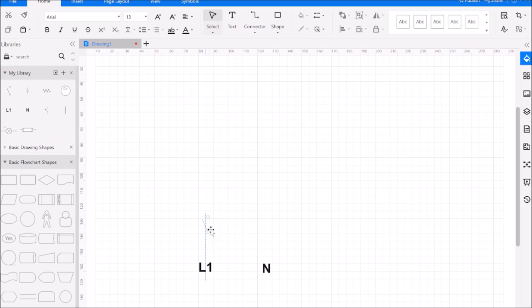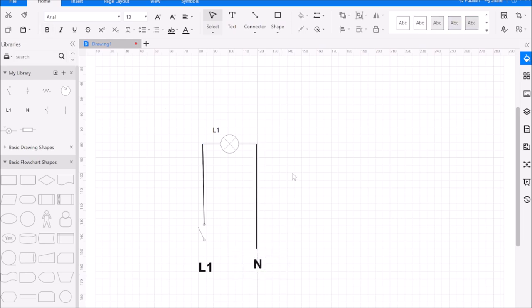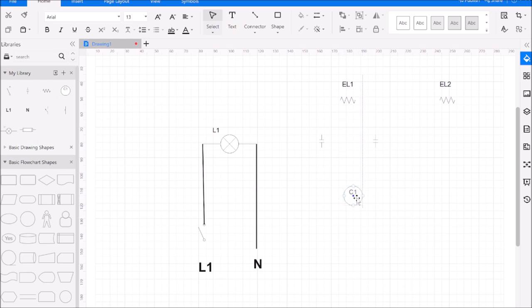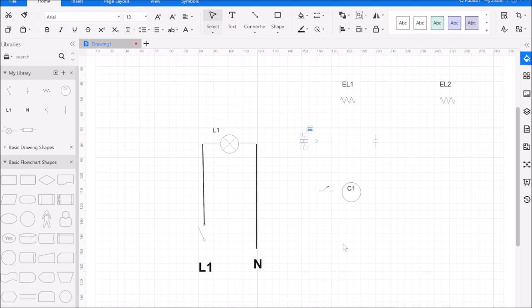First things first, let's identify our components. This is a switch right here and that's our light bulb — that's circuit one. We're just connecting to L1 and neutral. Here is circuit number two, which was our element — light equals element, we'll label it EL1. That's what an element will typically look like. We'll label the third circuit as EL2. This right here is a contactor contact — our contactor has two contacts — and this circle usually represents the contactor coil, so in this case it's our C1 contactor coil. Last but not least, we have a thermostat controlling the contactor coil.